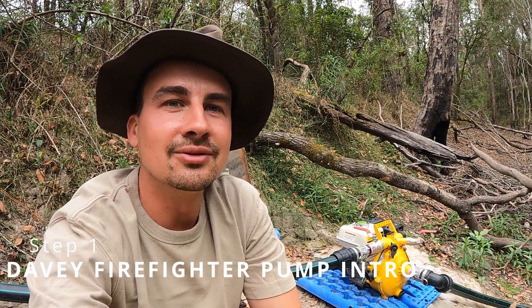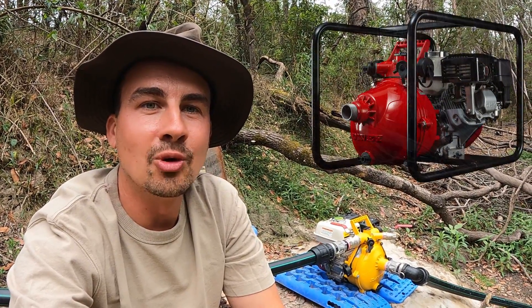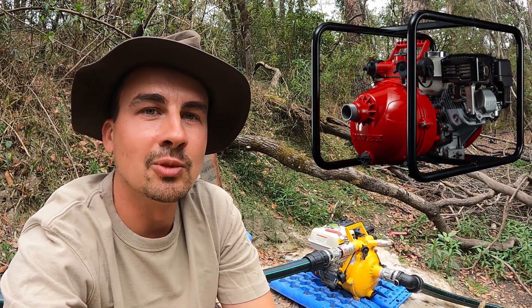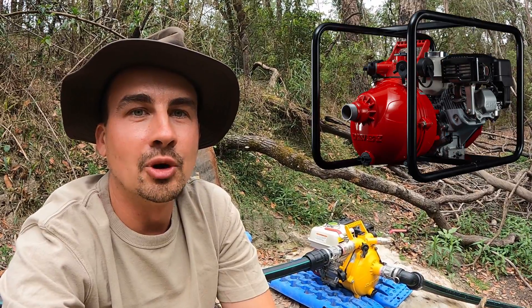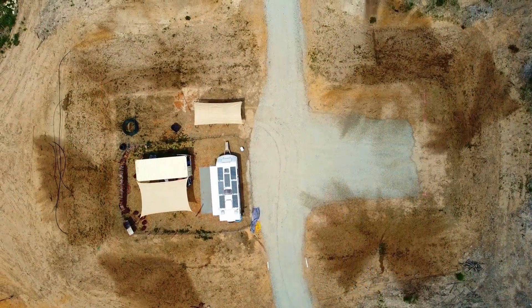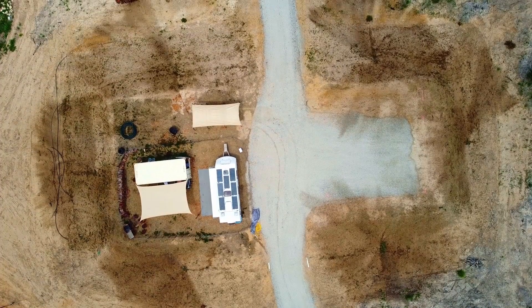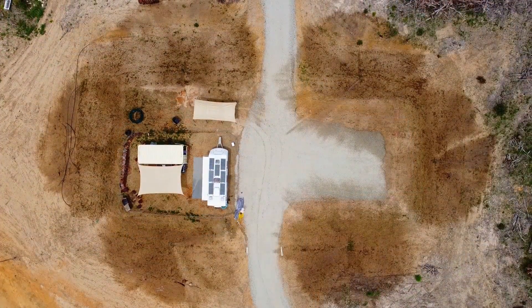G'day guys and welcome to this quick video on using a Davey firefighter pump like this one. This is the yellow Davey firefighter pump which means it's got a single impeller - the red ones are more hardcore basically and the yellow ones are the base models. Don't be fooled by it being a base model though - this pump can actually provide us with double the amount of pressure compared to what we need to run six sprinklers and two hydrant points.